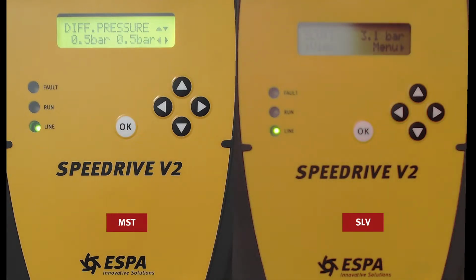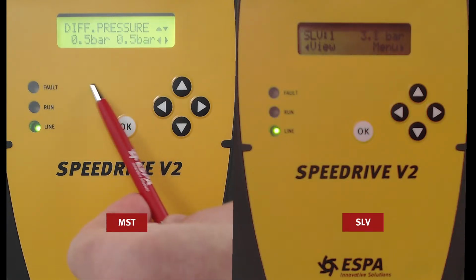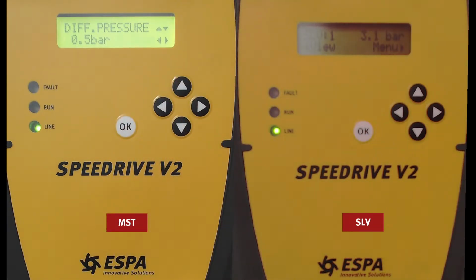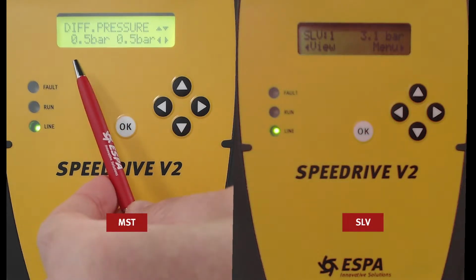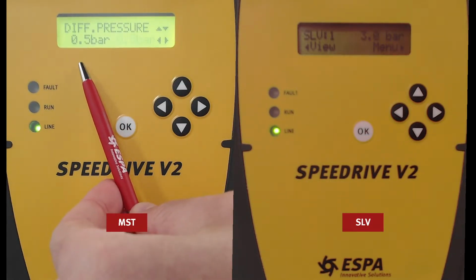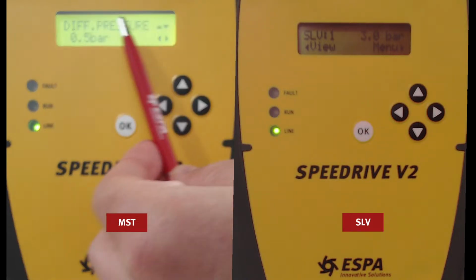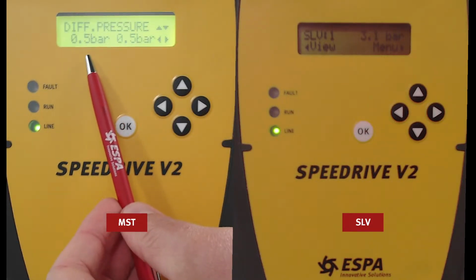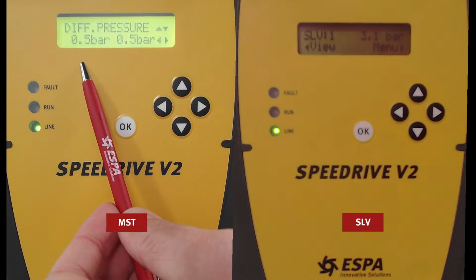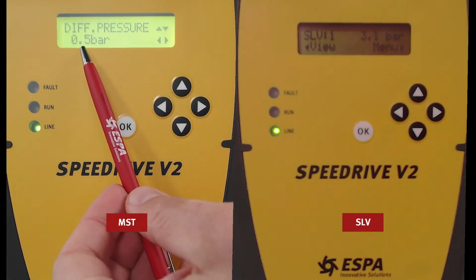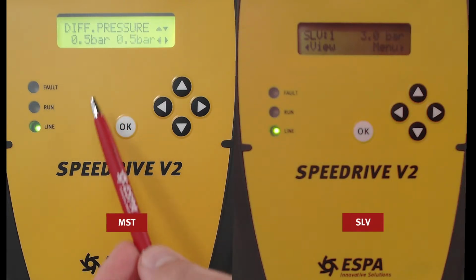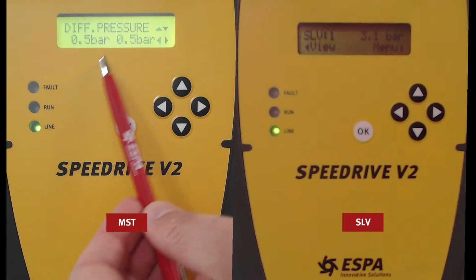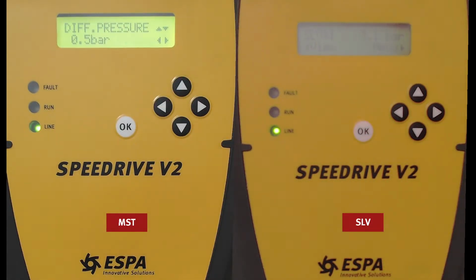Differential pressure, 0.5. What is this setting? The differential pressure is the pressure drop from the duty point at which the pump starts. For example, if we have right now 3 bar and we have a differential pressure of half a bar, the pump will start at 3 minus 0.5 bar. It will start at 2.5 bar. So this is the differential pressure.